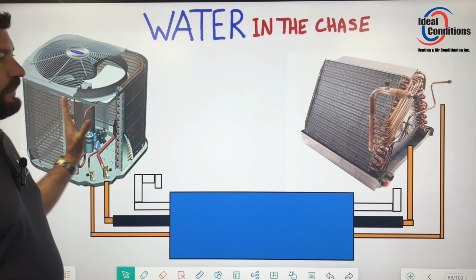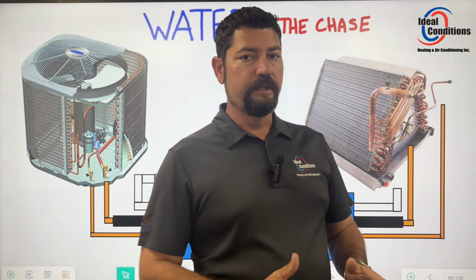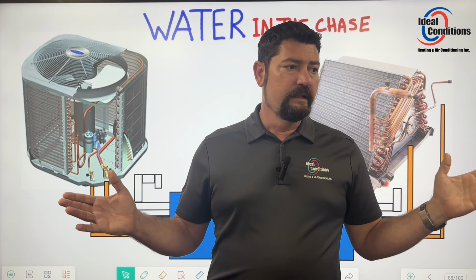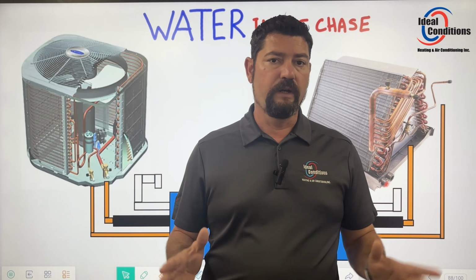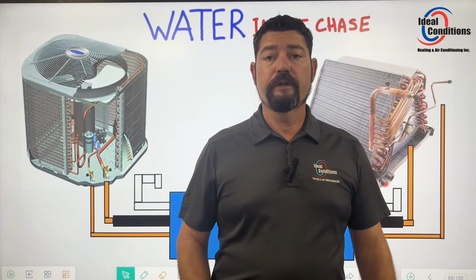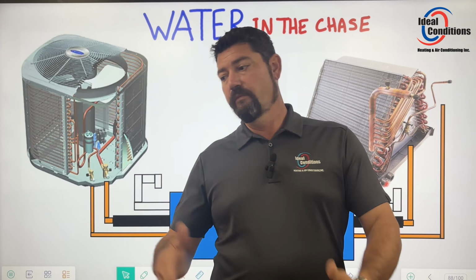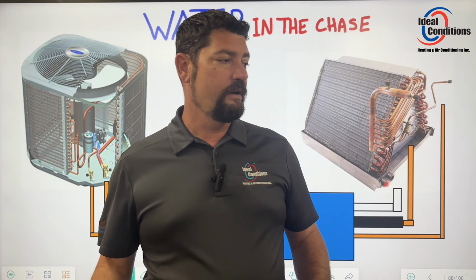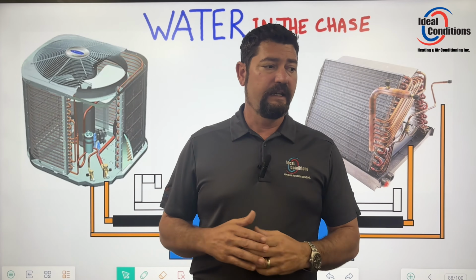And you know what? You could have a brand new air conditioning system that you just installed, and the chase was full of water, and it might have had, let's just say, 30 or 40 gallons of water in it. And guess what? You put a brand new system in, and within 2 months or 3 months, you lose a compressor. Somebody goes out there, they put a compressor in, 4 or 5 months later, you lose that compressor.